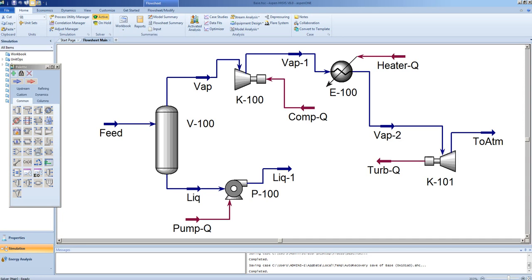So the flue gas from the combustion chamber, which is compressed gas, is passed through a turbine and brought back down to some much lower pressure, releasing energy that is picked up by the shaft. In most cases, the shaft energy is then shared between the compressor energy required and the remainder used to either generate electricity or as driving power for some other device or some other pump, etc.